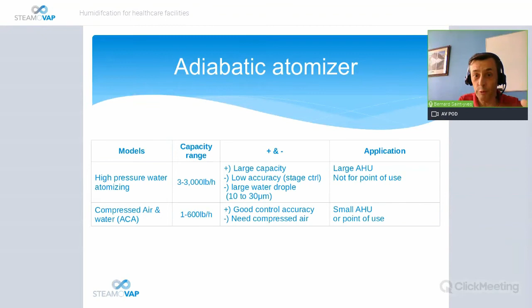The control accuracy is much better because we can control the valve, but you need compressed air, which they don't have most of the time in small facilities or in hospitals. And then the cost of operation will go very high because of the technology in the nozzles, and the nozzles are very expensive in ACA compared to the high pressure atomizer. So it's good for a small air handling unit or point of use, if an engineer really wants to use atomizers for healthcare.